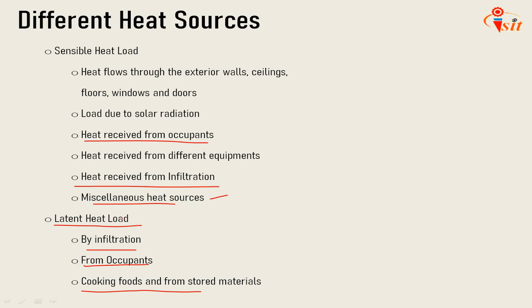Now the next slide is about the estimation of loads. Now the estimation of loads are listed here, but the primary requirement of cooling and heating equipment is that it must be able to remove or add heat at the rate at which it is produced or removed and maintain the given comfort conditions in the room. Now the proportion of sensible heat to the latent heat decides the sensible heat ratio, or it is also called the enthalpy humidity difference ratio, and hence also the condition at which the conditioned air must enter the room, because it lies on the line drawn from the room condition at the slope of the above ratios.